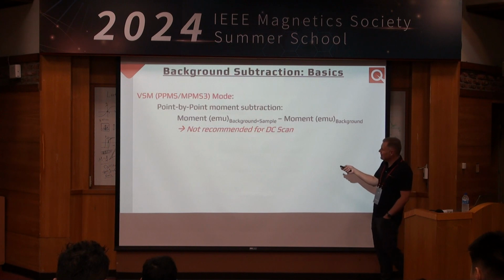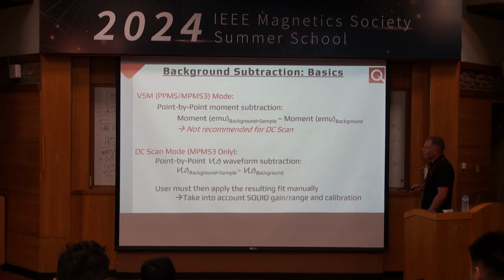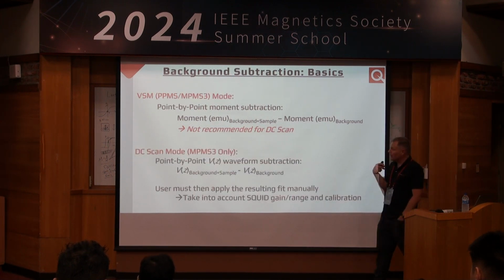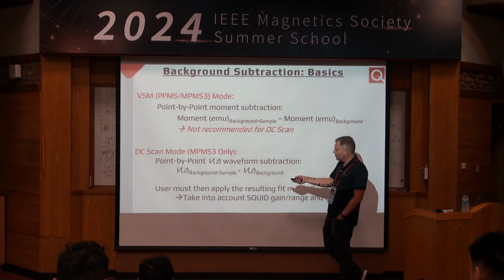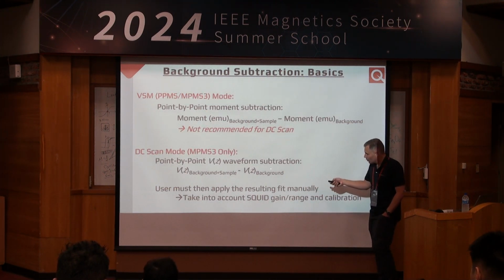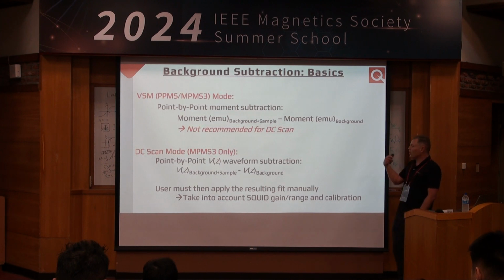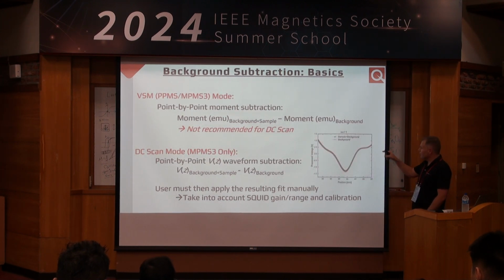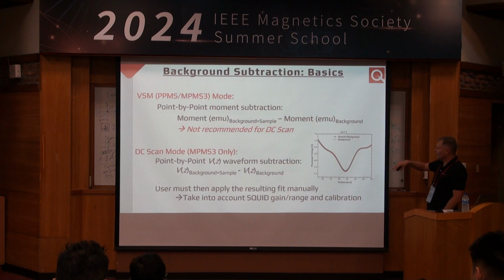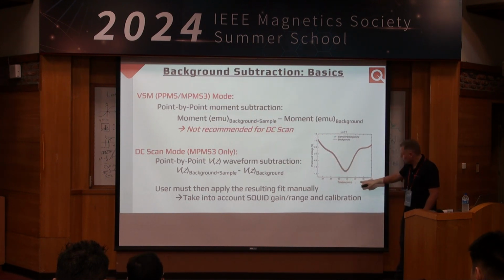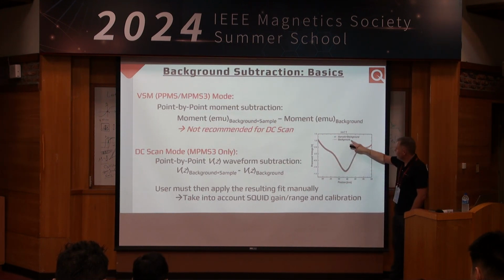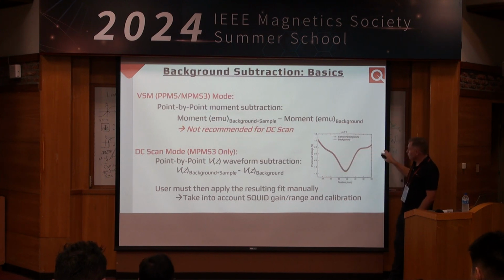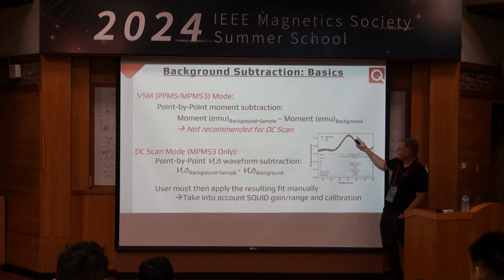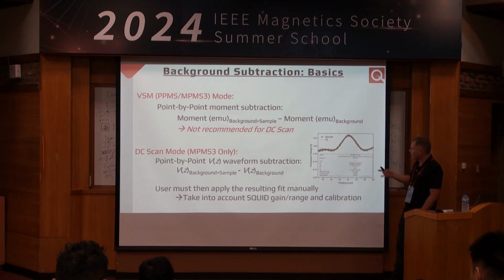But if you're using the DC scan mode for the MPMS3, now you have to be a little bit more careful because we calculate the moment based on that voltage waveform. So you technically need to subtract one waveform from the other and then refit this response. Here's an example of some measurement I did with a very large background. This is that voltage waveform, so position, voltage. Sample plus background, background. Almost no difference between them. So we have to subtract these, and now we finally get something that looks like the response we're expecting. Have to refit this and calculate the moment ourselves.